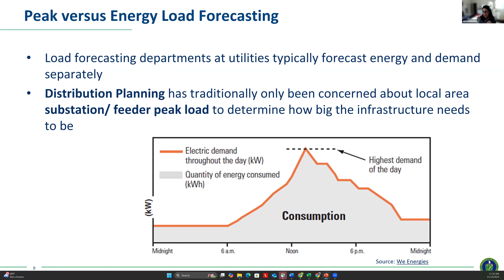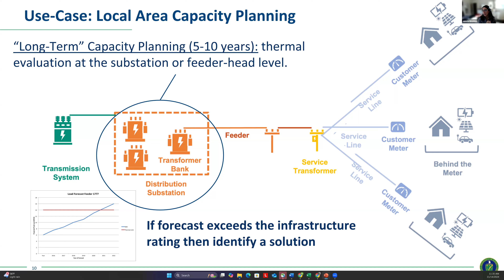Load and DR forecasting has typically been used in distribution planning for capacity planning, to evaluate that non-coincident peak demand with respect to the system peak, at the distribution substation or feeder head. If the forecast exceeds the rating in the 3 to 5, or 5 to 10, year time frame -- though it's typically been a short-term look in distribution -- then if it exceeds the rating of the asset, you come up with a solution. It could be wires or non-wires.